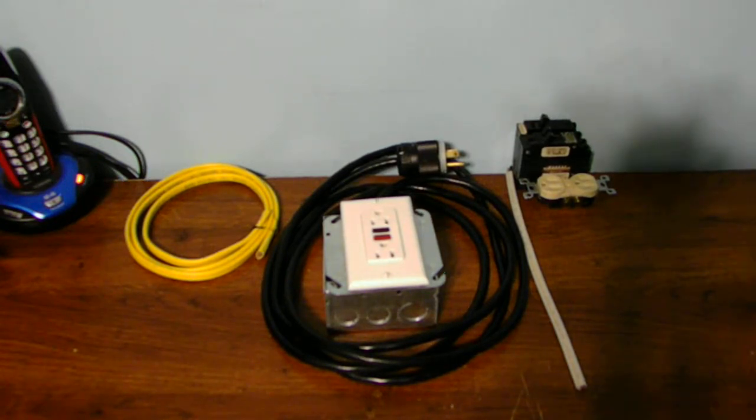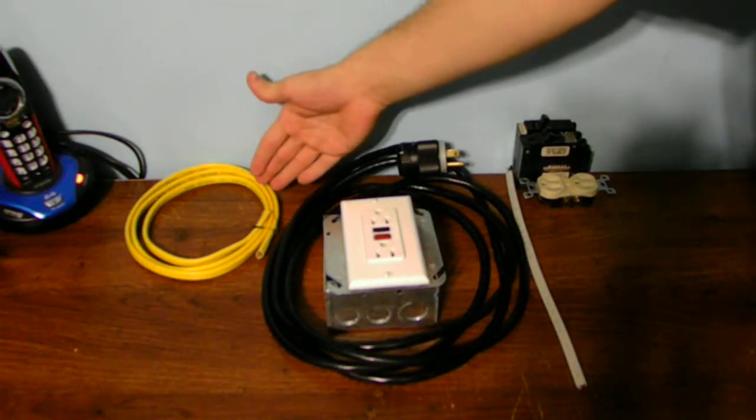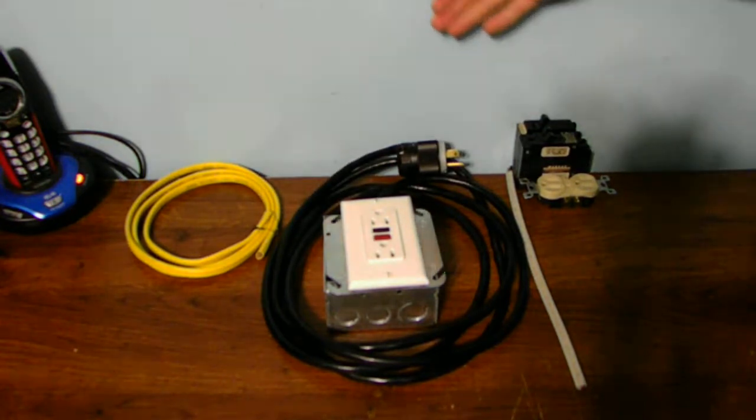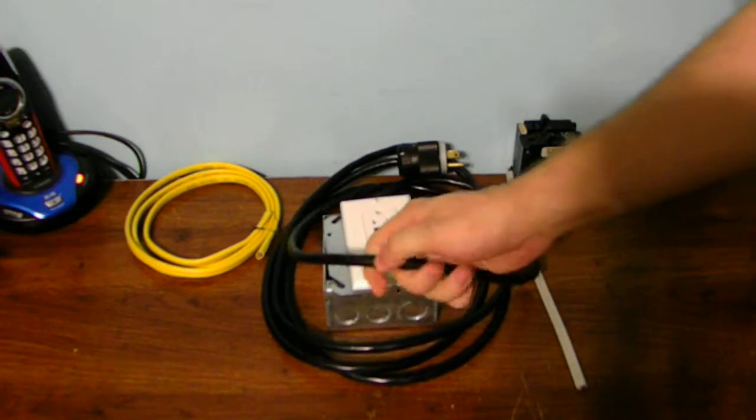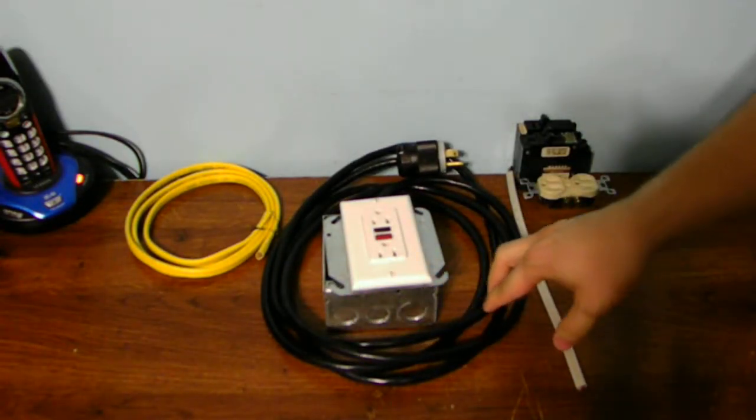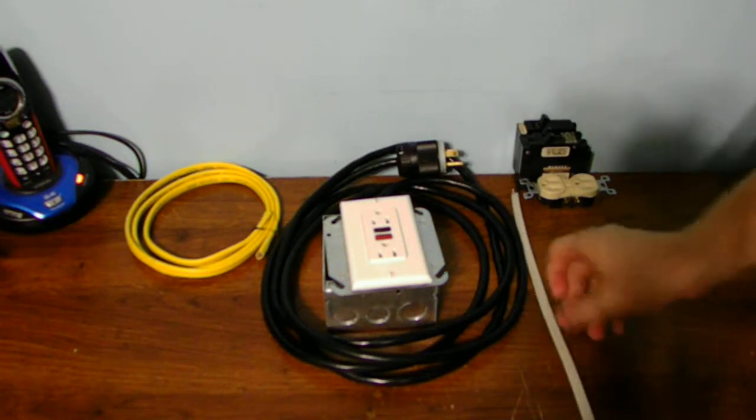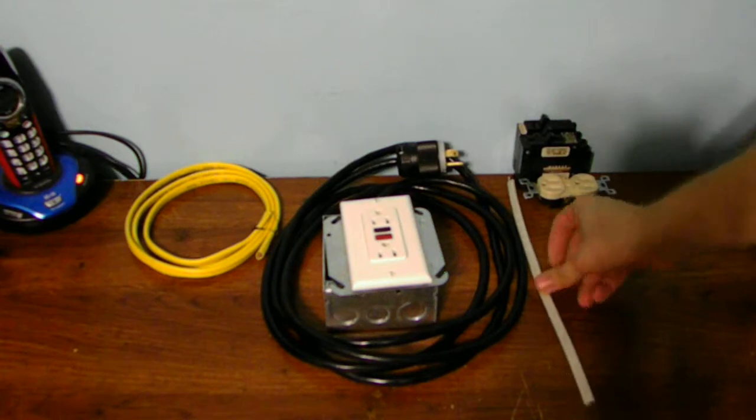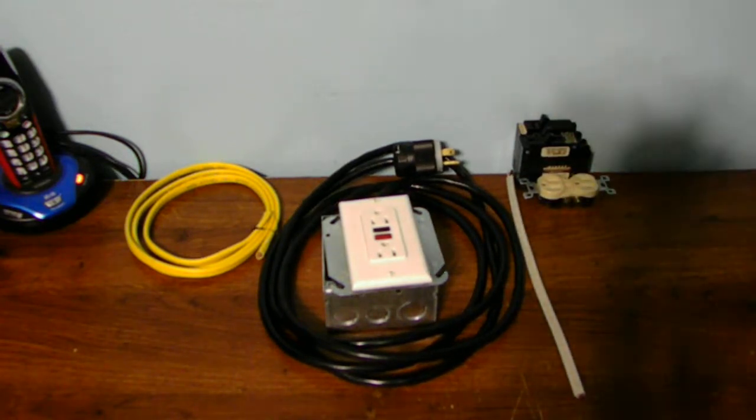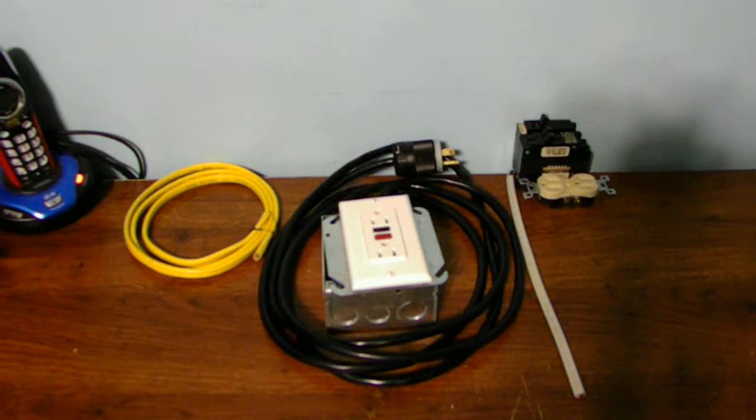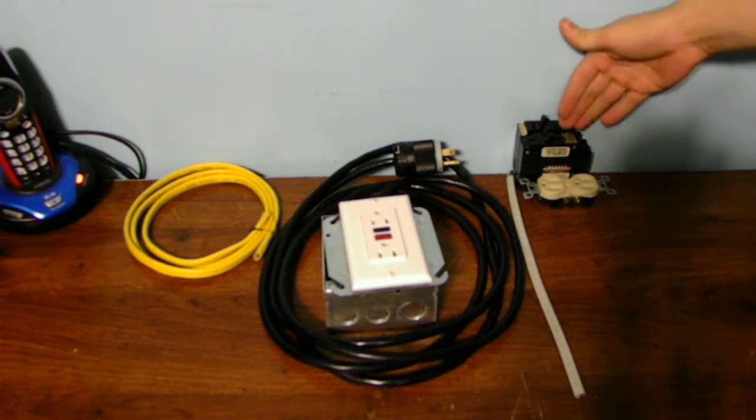Now, a lot of people don't understand this and the reason why we have electrical code for the different types of gauge wire we use. Alright, on this side, we have a Romex 12 gauge heavier duty wire on this side. We have a flex cable here. This is what's in this rubberized sheath. This is actually a 14 gauge soft cable or a stranded cable. We also have a non-stranded cable right here. This is a 14 gauge cable as well. This is for 15 amp circuits for 15 amp outlets. This is meant for 15 or 20 amp circuits right there for higher current.